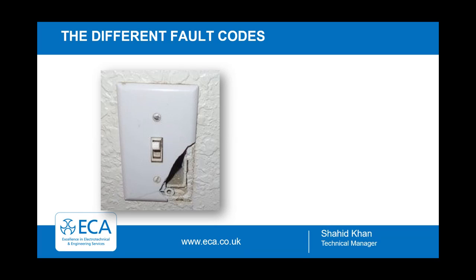dangerous. Oh, we've had a comment come in from somebody saying it's a C2. Is it a C2 or is it a C1, do you think, if we've got access to live parts there? Gary, if it was just a crack and that wasn't missing, would you then look at that as being a C2? But because you could actually stick a finger in, we're now getting into danger and current danger.